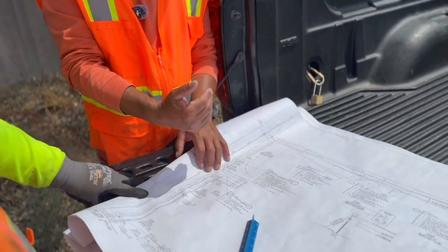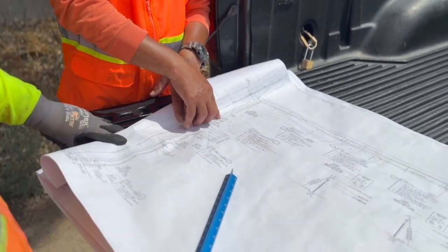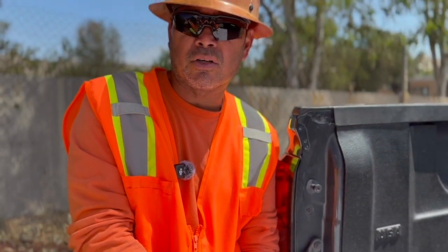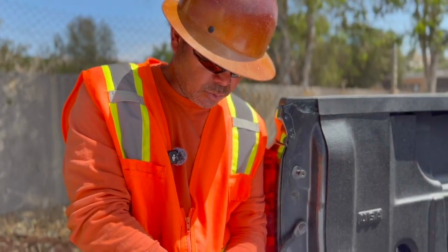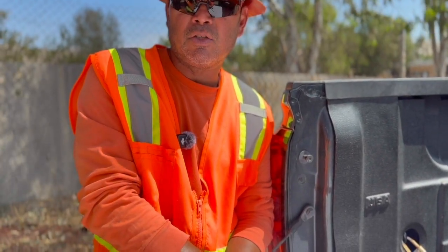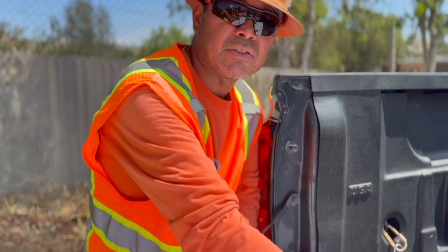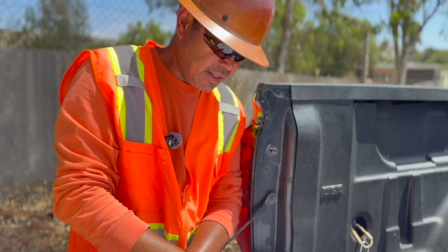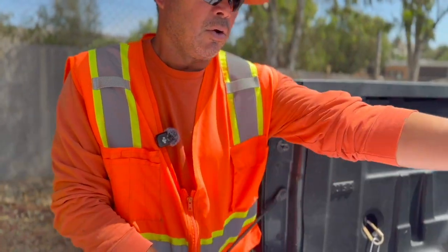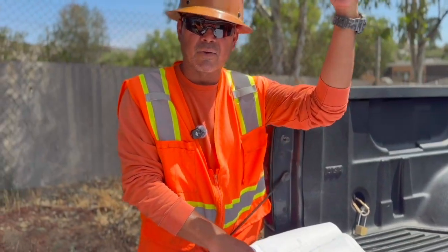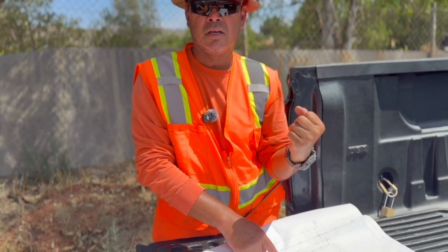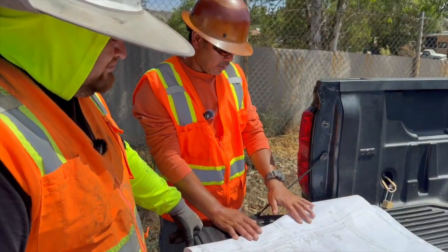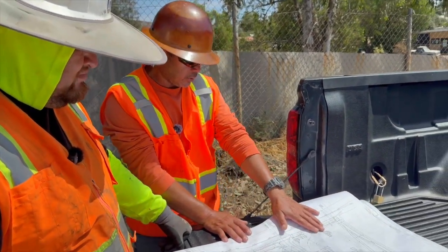Yes. Going back to what I was speaking about previously, this is the one where they put the transformer on top of the box, where they can do the disconnections or turn off the power. So this one has that ability. In this one, the power transfers only through splicing inside, but it's not a disconnection point. If they need to disconnect the power, they have to come right here, or maybe go to the riser. Sometimes in the riser they have a switch disconnection, and this one is just a splicing box pretty much.